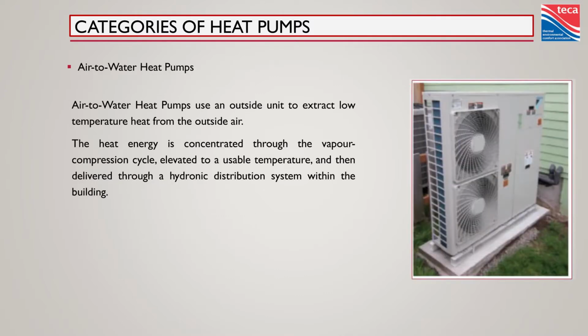So here's a classic air to water heat pump. In fact, this is kind of vintage. You can't even buy them anymore. This particular product's not on the market anymore, but this is an air source monoblock heat pump. So when we get into air to water heat pumps, we have subcategories. Monoblock is kind of a European name, but it's stuck. It is a packaged unit. So for those HVAC folks in the room, rooftop units, refrigeration's already self-contained. You just hook up some ductwork. Same idea. Hook up some water lines.